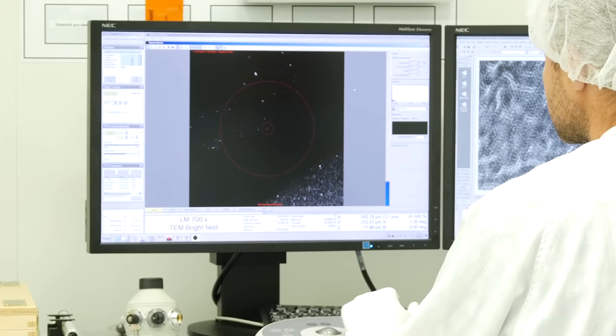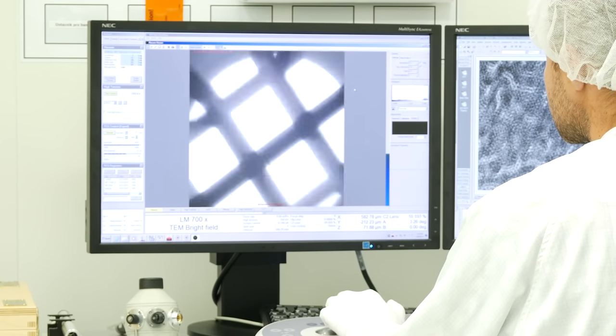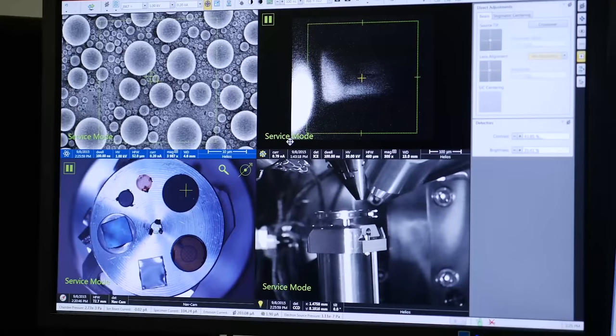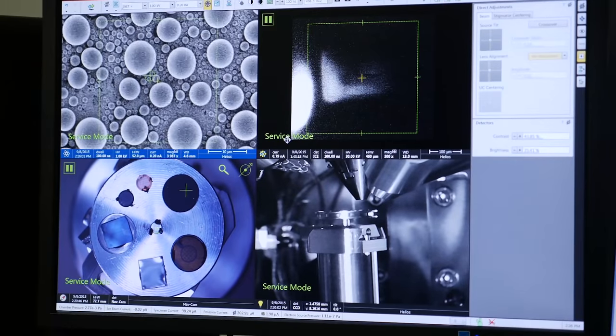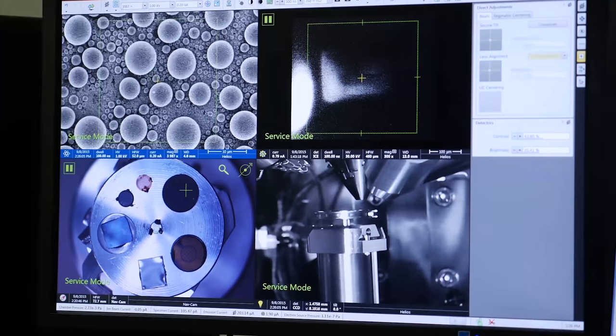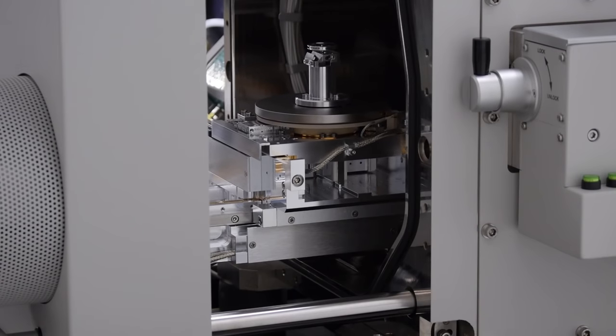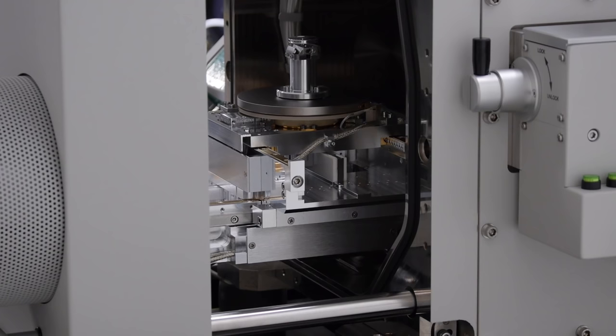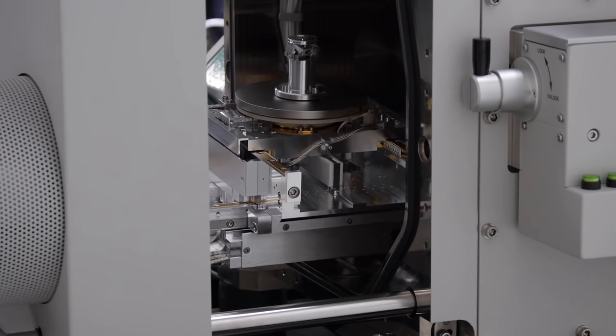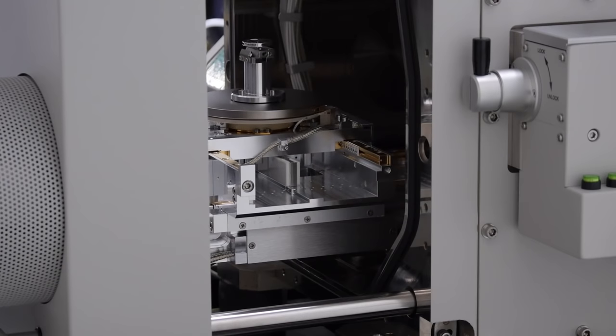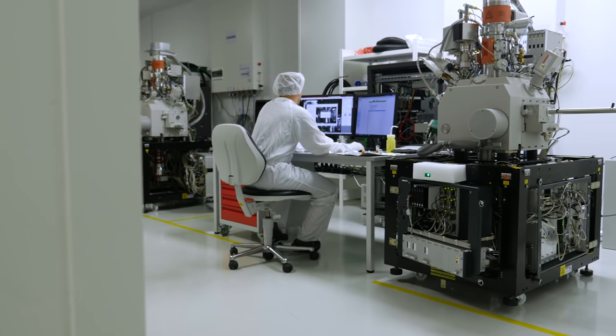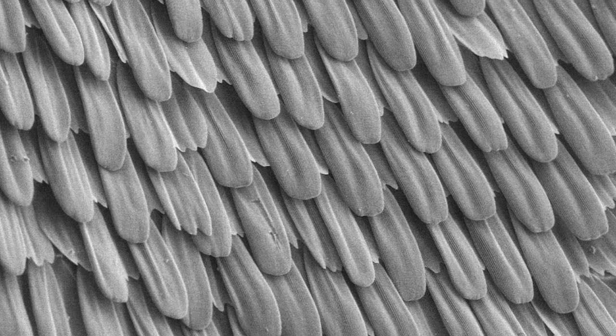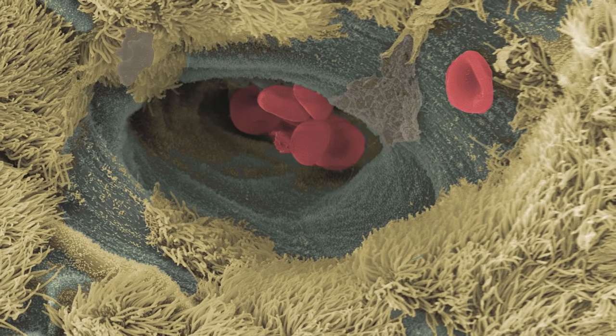Also, the rotation or movement along the z-axis in parallel to the electron beam. Phew, that sentence is a little complicated. It would be enough to say, yes, it's possible. We'd better move on. What influences the quality of the picture? The image quality in the scanning microscope depends on the orientation and distance of the sample from detectors and the final lens. The stage on which the sample is placed makes it possible to move it horizontally along the x- and y-axes, up and down, in the direction of the z-axis, and with a possible inclination and rotation. These movements are performed with step motors and are controlled by the computer. Great, but show me some pictures already.